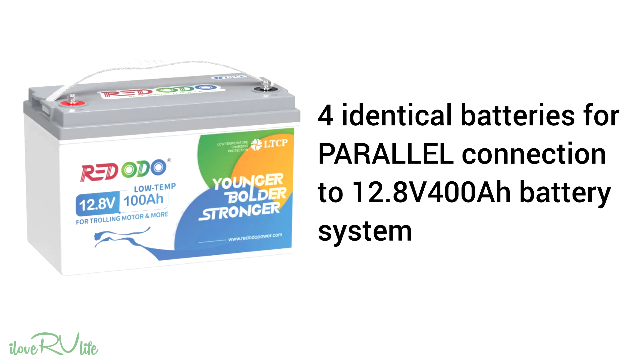As with most of the lithium batteries you're seeing today, the BMS will support four identical batteries either in parallel or series. You'd put these in parallel to get a 12.8 volt system at 400 amp hours, letting you start with one and build up. Or if you want a 48 volt system, it actually comes out to 51 volts at 100 amp hours, so you can put four in parallel, four in series.